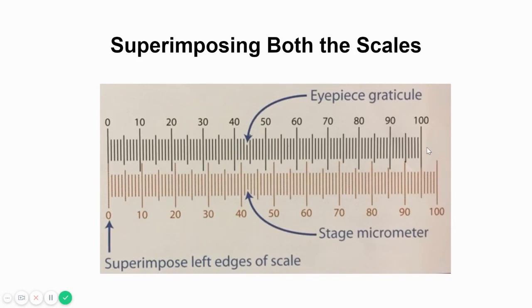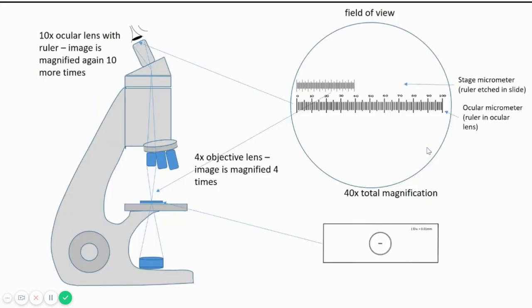Provided, remember, when you change the magnification, that is when you change the objective lens of your microscope, this lens, you will have to calibrate again. When you change the objective, the size of the stage micrometer keeps on changing. When the stage micrometer size keeps magnifying or shrinking every time you change the objective lens, you will have to recalibrate your eyepiece graticule. Calibration means eyepiece graticule divisions are unknown units. We want to find out, basing on the stage micrometer length, what is the eyepiece graticule scale.